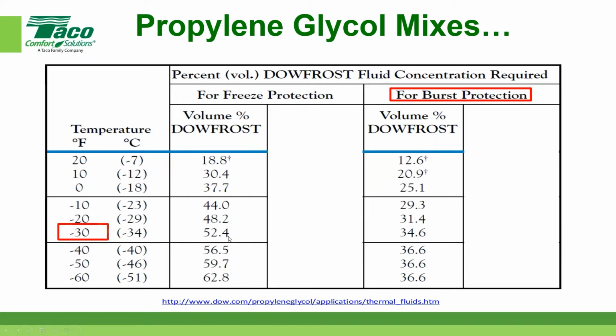Okay, that's not typically what we do under a design condition. Remember what a design condition is. It's the condition at which the system would be fully up and operational and going to beat the band. For instance, the boiler is approaching its maximum firing rate. The pump is up to its maximum speed. The fluid temperature is up at a design condition, etc. Okay. Now look over here.